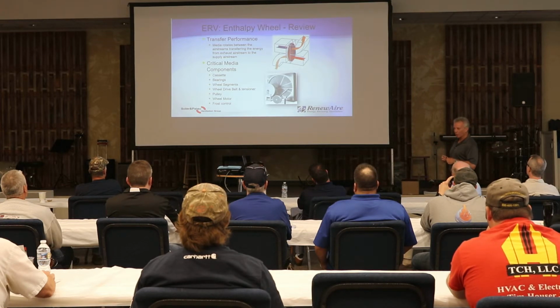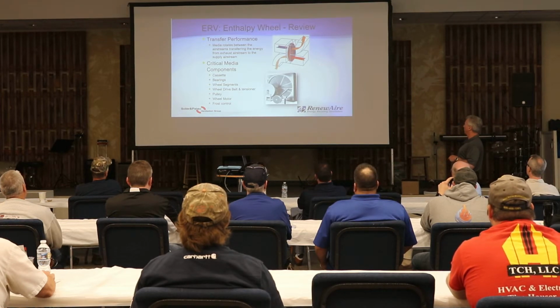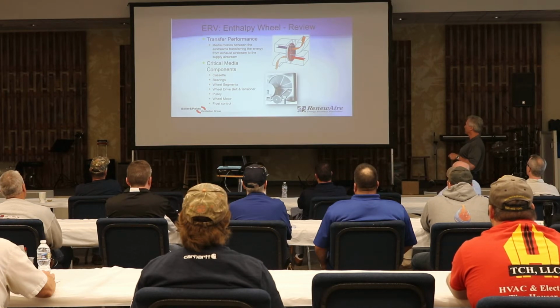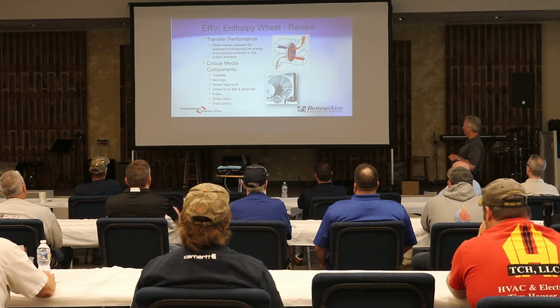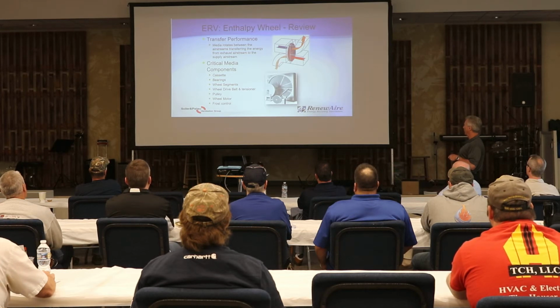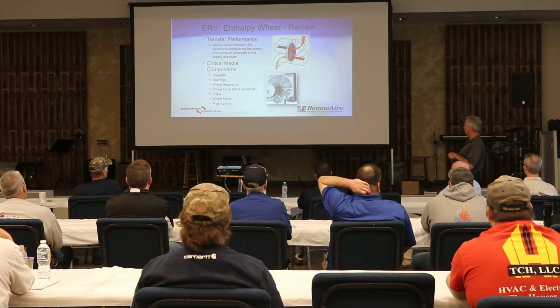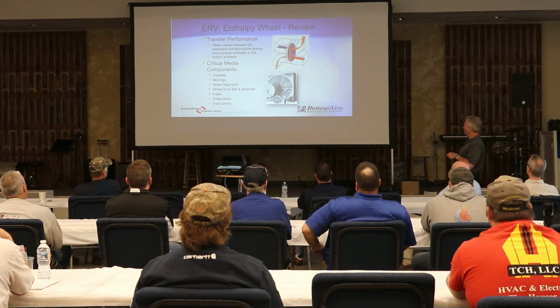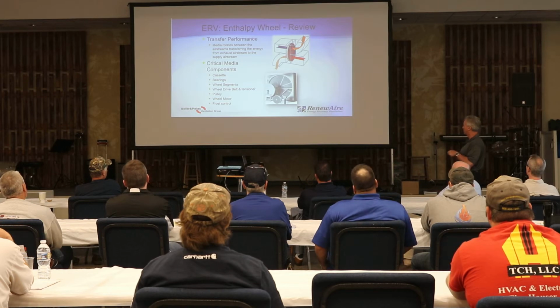Again, this really is a commercial product, but just so you are fully informed, this gives you an idea of what happens on a desiccant heat wheel or an enthalpy wheel. You've got exhaust air crossing through the wheel material. By the way, that wheel is rotating constantly. You've got exhaust air moving through the wheel on one side. As it turns, it will absorb heat and moisture and turn into the other airstream, and it gives up that heat and moisture.